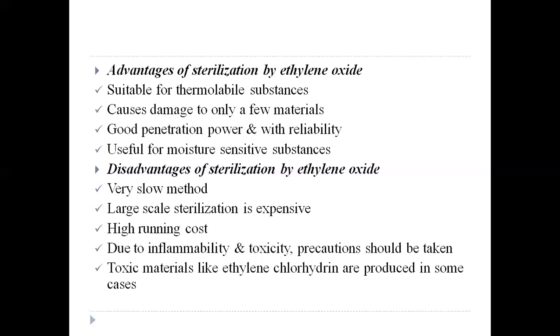The second one is it can cause damage to only a few materials. You know, ethylene oxide is a very reactive compound, but it has been seen that in spite of being a reactive compound, the damage done to the materials or the substances is very minimal, and it can damage only very few materials. So that is another advantage of sterilization by ethylene oxide.